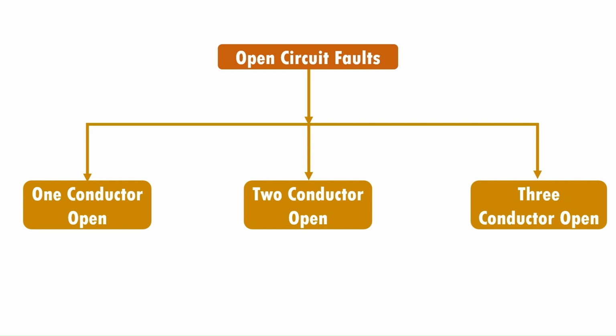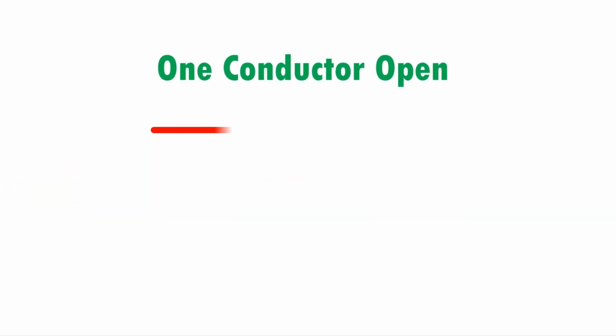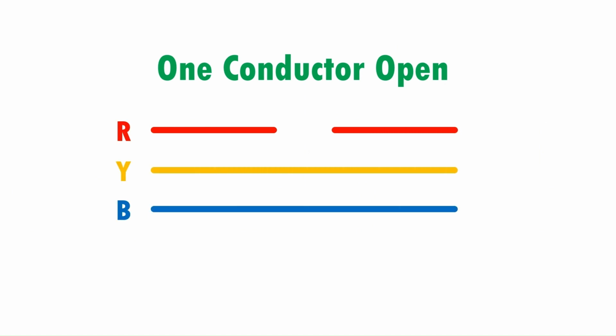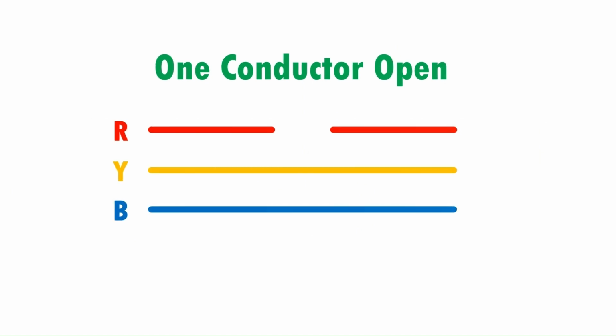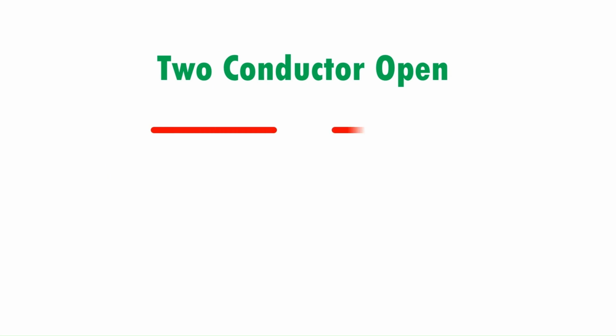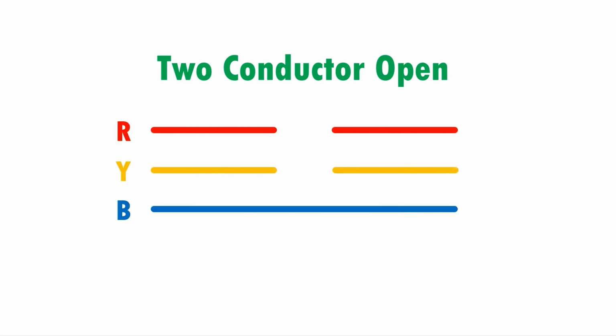The open circuit fault is categorized into one conductor open fault, two conductors open fault or three conductors open fault. In one conductor open fault, any one phase out of three phases gets open. In two conductors open fault, two phases out of three phases get open, and in three conductor open fault, all the phases are open.